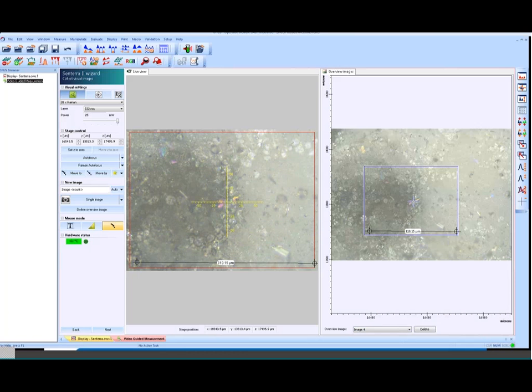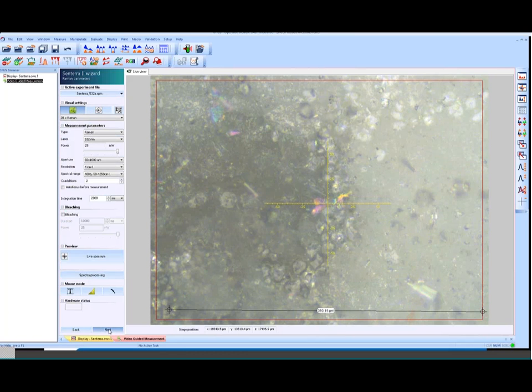And in the next step of the video wizard, we will get the parameter settings page. So here we have lots of options to tune our experiment. We can select the appropriate laser wavelengths. Changing of the laser takes less than 1 minute, and then you will see the spectra popping up with another wavelength. We'll stay for this experiment at the green laser line. We can tune the laser, apertures, and also the measurement time for this fast imaging measurement.